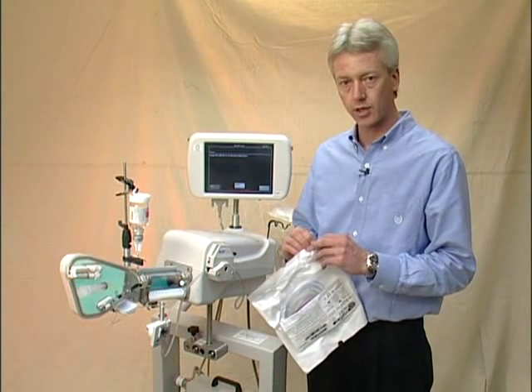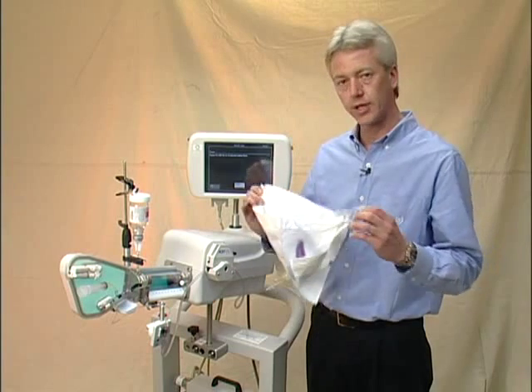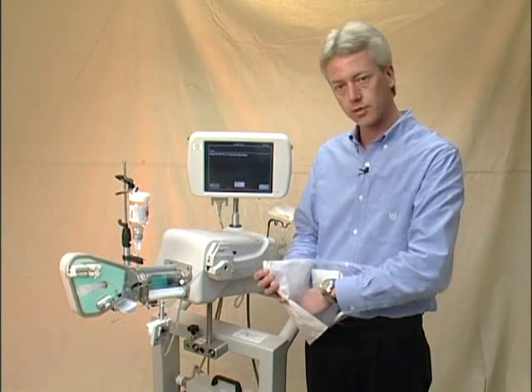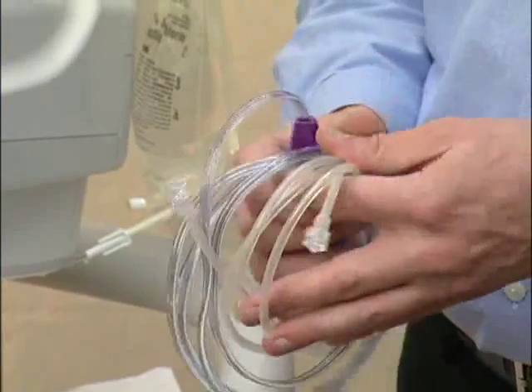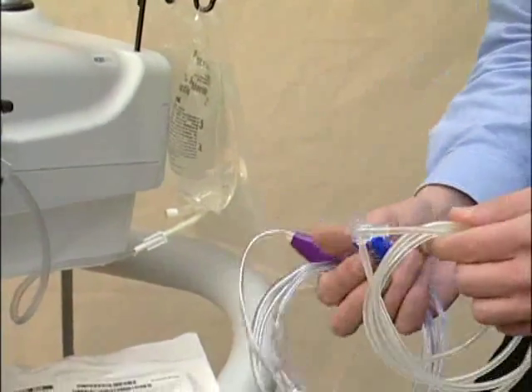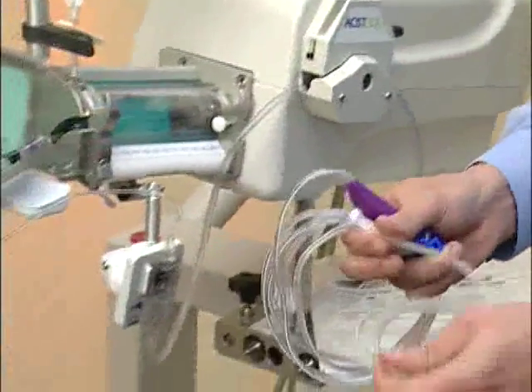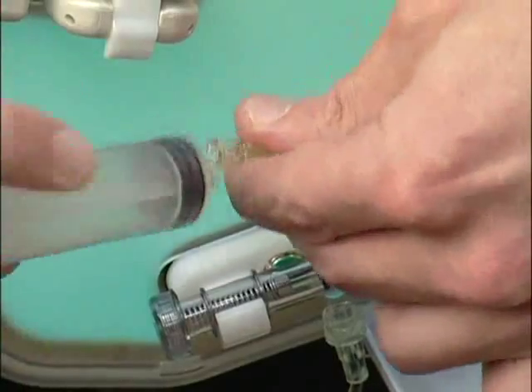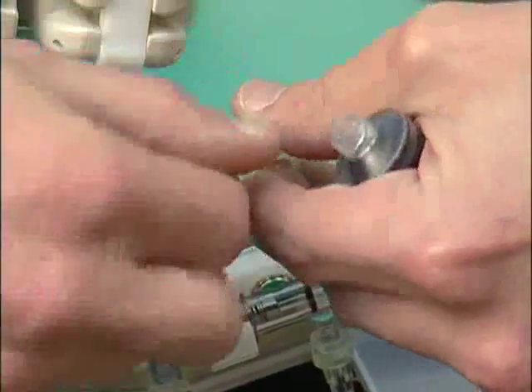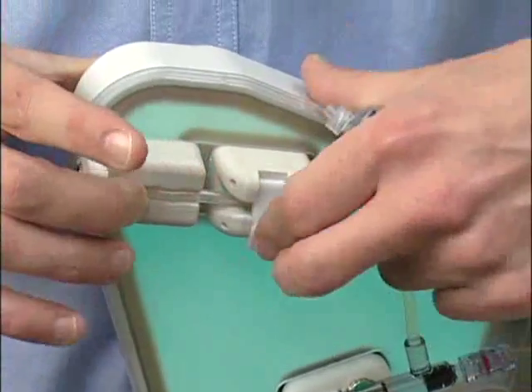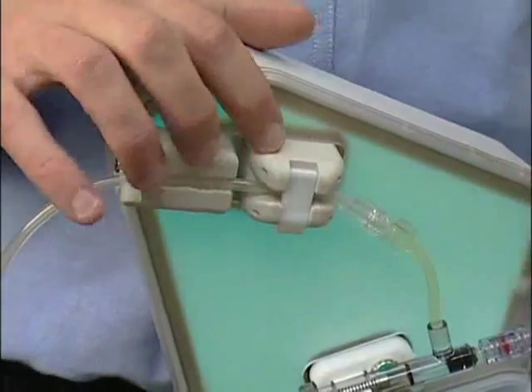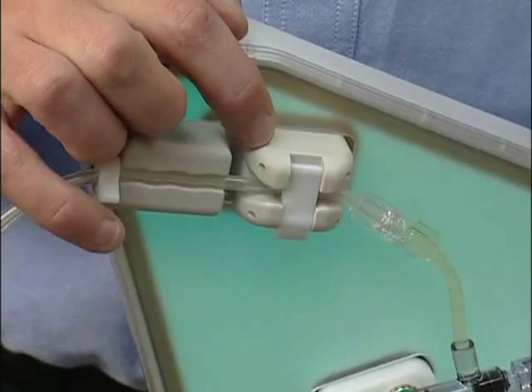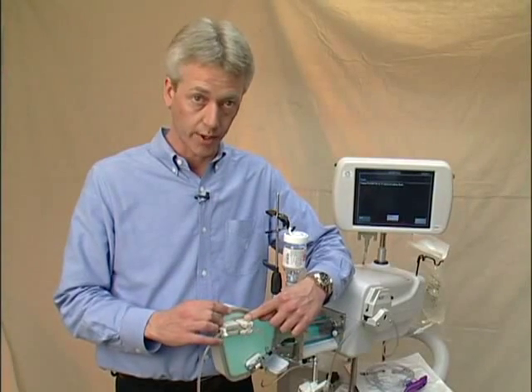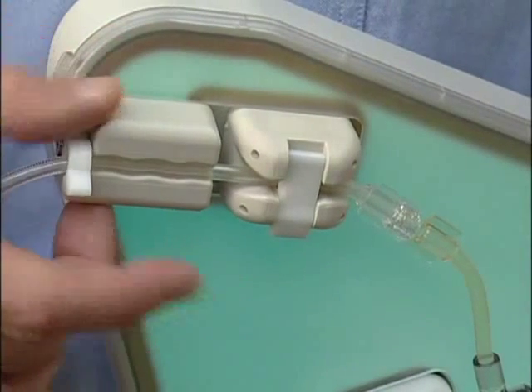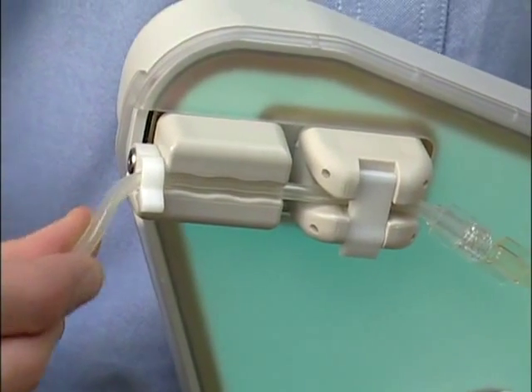Now we're opening up the sterile hand controller pack. This pack is generally dumped onto the sterile tray or onto the X-ray table. We'll take the high pressure line and connect it to the end of my manifold. The high pressure tubing is connected to the manifold line. Make sure there's a tight connection. My high pressure tubing is inserted into the air column detect. Now the air column detect sensor is a secondary device for monitoring air. The primary device will always be the operator's own two eyes. The strain relief on the front provides support so there's no false triggering of the air column sensor.